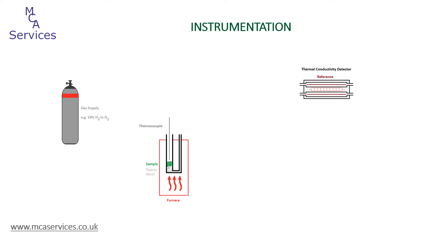We're now ready to introduce gas flow. Here at MCA Services for TPR, we use a blend of 10% hydrogen in nitrogen. The critical thing to consider when selecting gas mixtures is that they must have a reasonable difference in thermal conductivity — between the active component, the hydrogen, and the inert carrier. The thermal conductivity of hydrogen is about seven times higher than that of nitrogen, so there's a really good difference there, because we're going to be measuring what happens at the TCD when hydrogen is taken out of the flowing stream and consumed by the sample to reduce it.